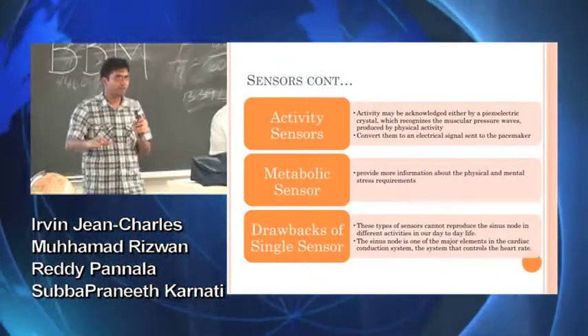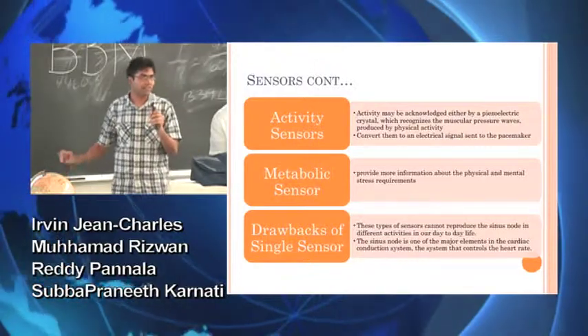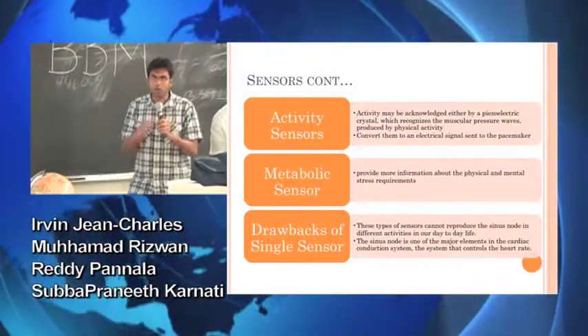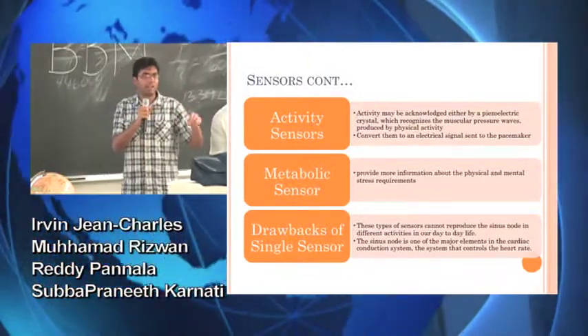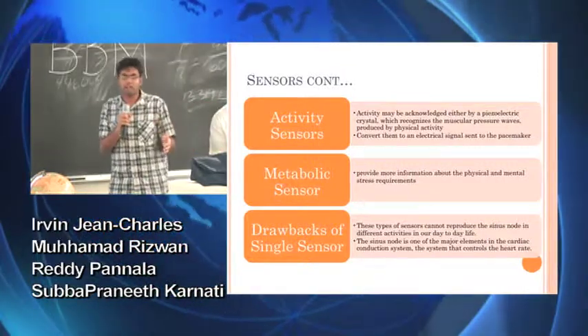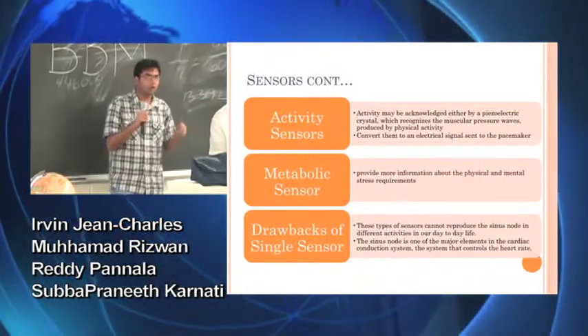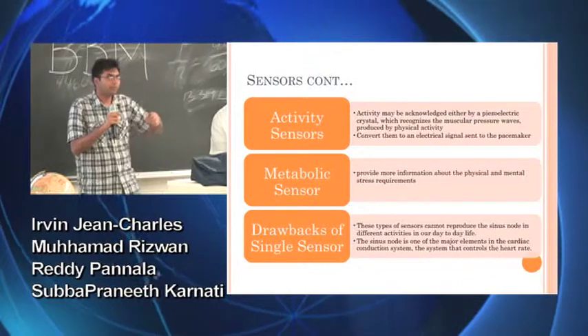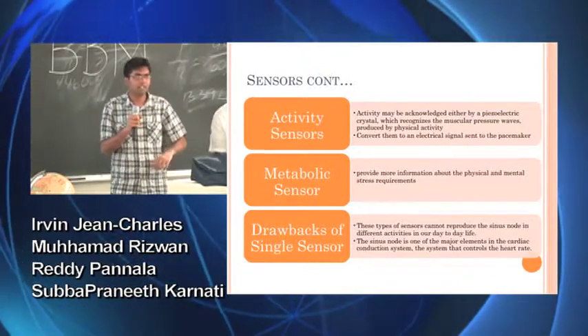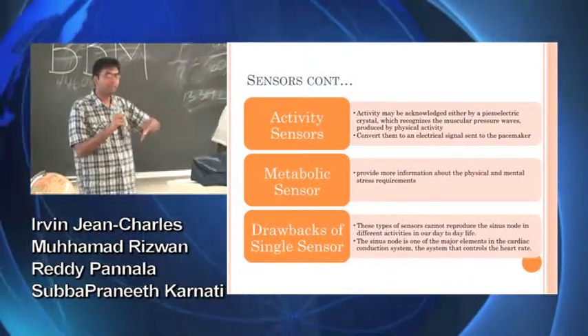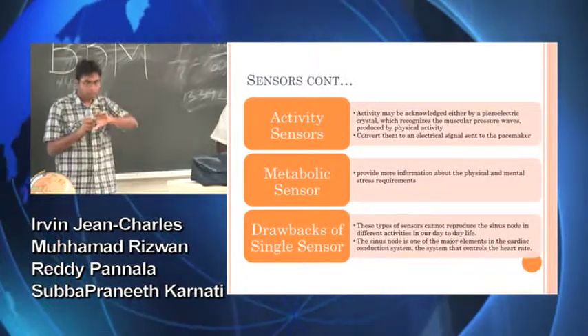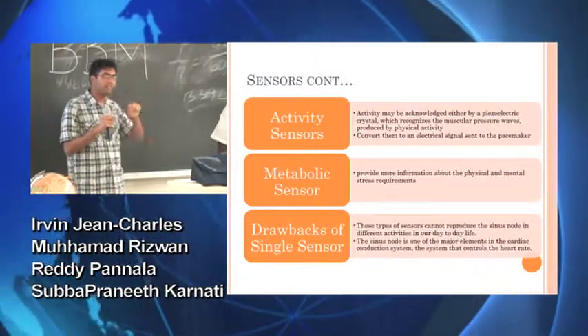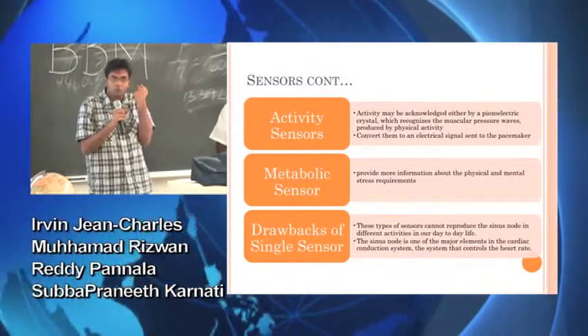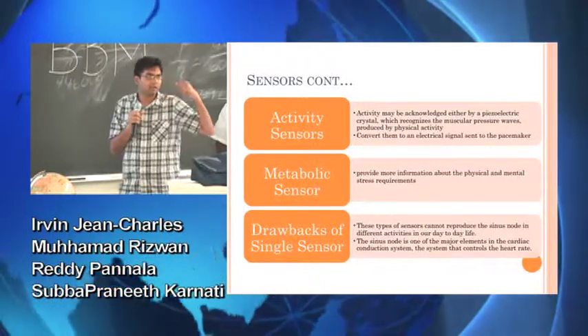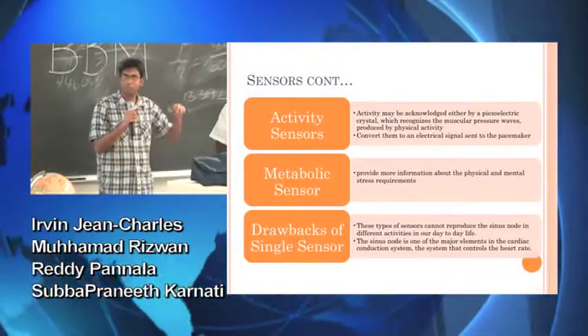Let me briefly explain the important sensors that they're going to use: the activity sensors and the breathing sensors. The pacemaker is going to give the electrical impulse to the heart, but the pulse generator has to know if I'm doing exercises, sleeping, or working, because the heartbeat is going to be different for different periods of time. The pacemaker has to know what the heartbeat should be if the person is doing exercise, and what it should be if the person is sleeping.